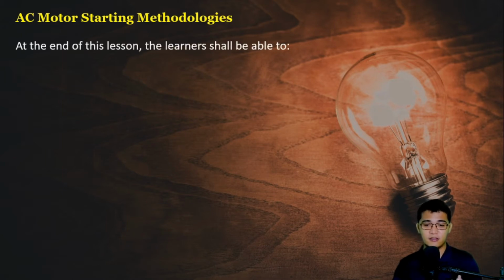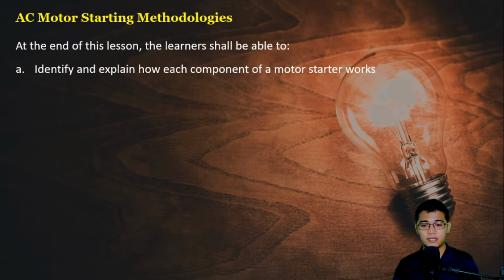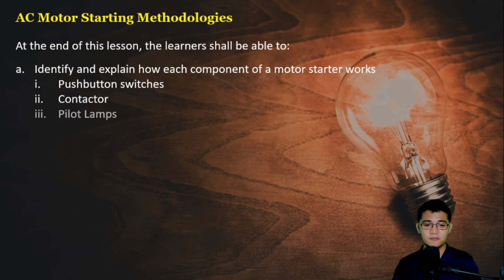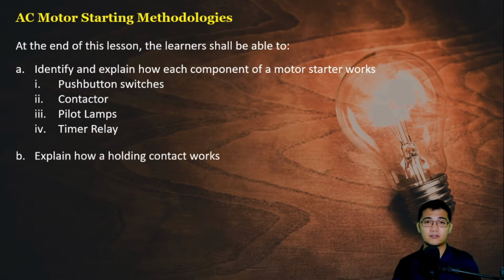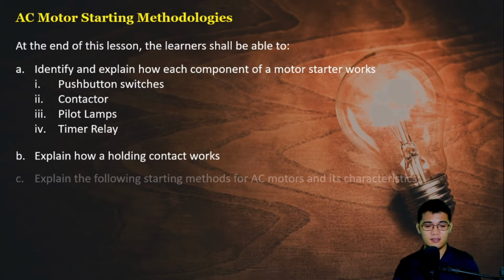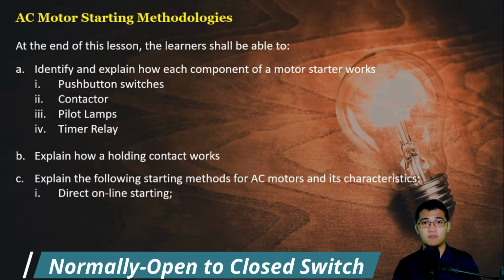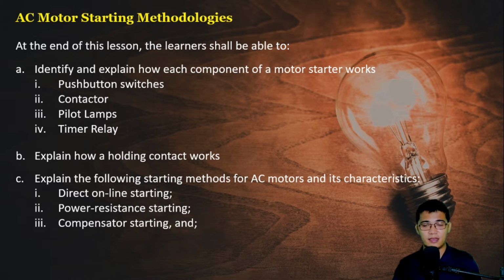At the end of this lesson, the learner shall be able to identify and explain how each component of a motor starter works, specifically the push button switches, the contactor, the pilot lamps, and the timer relay. We will also explain how a holding contact works, and lastly explain the following starting methods for AC motors and their characteristics: the direct online motor starter, power resistance starting, compensator starting, and star delta motor starting. So without further ado, let's start.